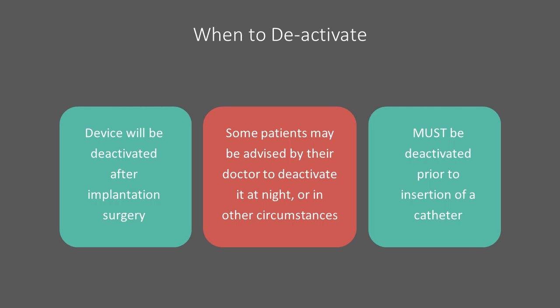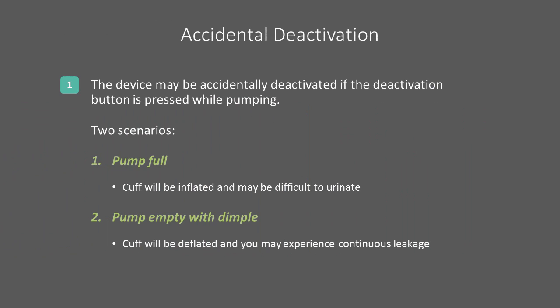As noted, it is very rare otherwise to have to deactivate it. Certain patients may be advised by their doctor to deactivate it at night or in other circumstances. Of note, it must be deactivated prior to insertion of a catheter. The device may be accidentally deactivated if the deactivation button is pressed while pumping. In these cases, two scenarios may play out. First, if it is deactivated with a full pump, the cuff will also be full and you may find it difficult to urinate. In other situations, however, if it is deactivated with the pump empty, the cuff will also be deflated and you will probably experience continuous leakage. The next two slides address each of these situations.